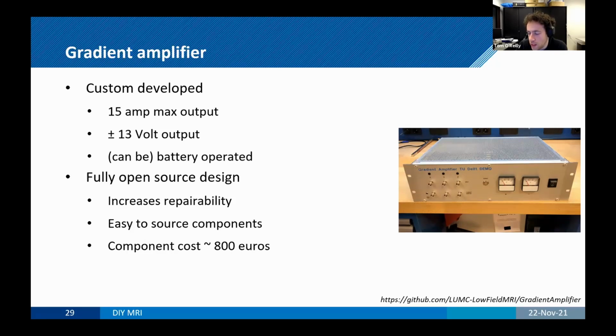For the gradient amplifier, typically for high field systems, they're switch mode amplifiers. So they will have switching electronics inside of them, and switching electronics are noisy. And at high field, it's easier to filter out those noises because you're so far away from DC. Whereas for low fields, 2 megahertz, it becomes a little bit harder to filter these out. So a lot of commercial vendors will sell you gradient amplifiers, claim that they're low noise, but when you hook them up, they're terrible. So we ended up just developing our own little amplifier. It's much weaker than conventional systems because we want it to be battery operated potentially. Again, because eventually we plan on having one of these systems in Uganda where the power grid is just not very reliable. So we can operate these with batteries. We typically don't because it's easier not to have to charge them all the time.